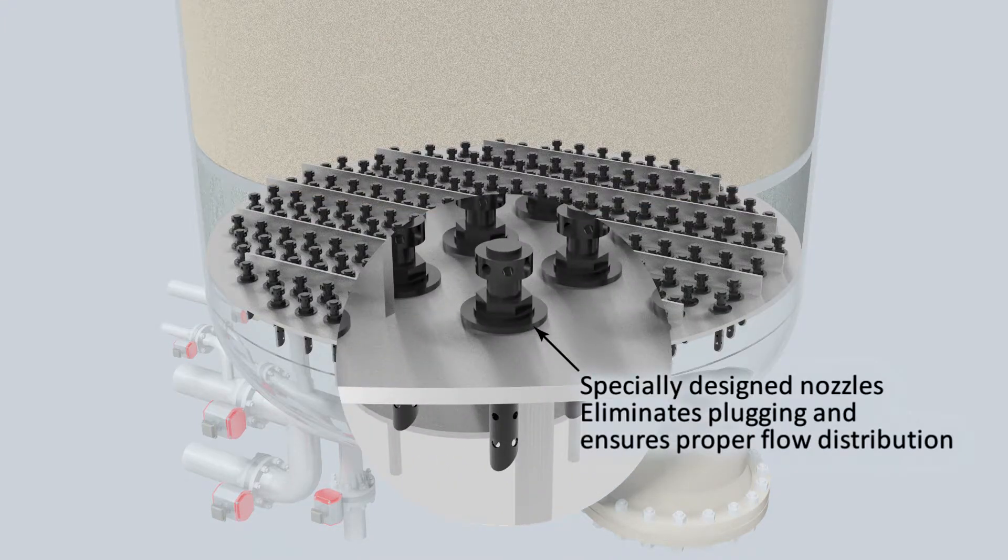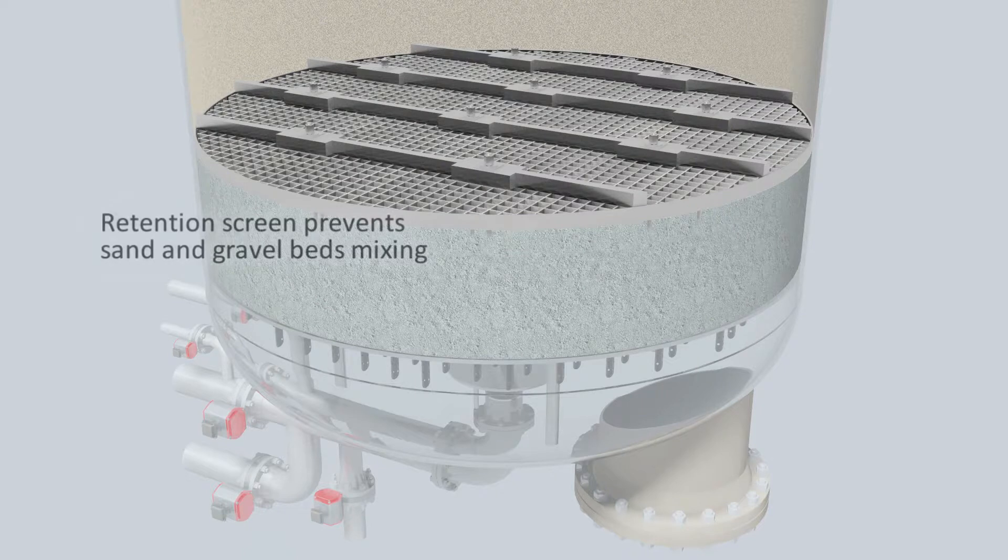The inlet distributor is a deck plate with nozzles sized for uniform flow distribution. A media retention screen is installed between the gravel and sand interface. The screen keeps the gravel from mixing with the sand.